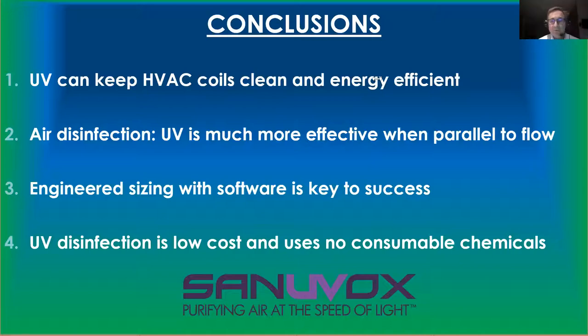Well, by multiple reflection between the fins, they do get there, but they get there with lower intensity. That's why you need more time to clean all the way through. The immediate surface where the light is seen directly would get clean in a matter of minutes, whereas the back end of the coil, depending on the thickness of the coil, will take anywhere between a few hours and sometimes close to a day before it goes through.